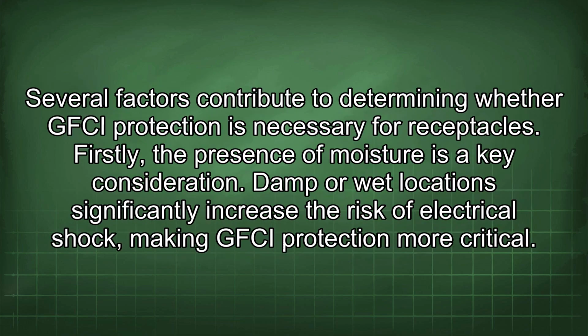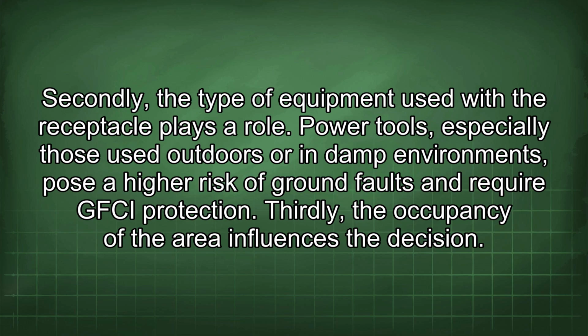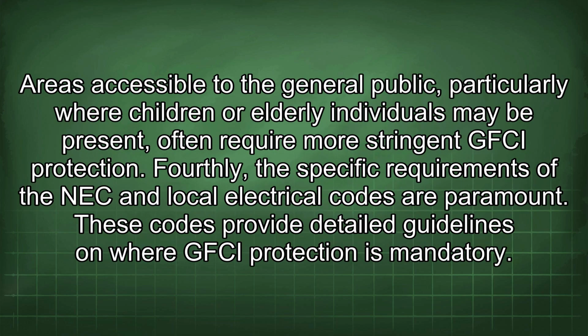Several factors contribute to determining whether GFCI protection is necessary for receptacles. Firstly, the presence of moisture is a key consideration. Damp or wet locations significantly increase the risk of electrical shock, making GFCI protection more critical. Secondly, the type of equipment used with the receptacle plays a role. Power tools, especially those used outdoors or in damp environments, pose a higher risk of ground faults and require GFCI protection. Thirdly, the occupancy of the area influences the decision. Areas accessible to the general public, particularly where children or elderly individuals may be present, often require more stringent GFCI protection. Fourthly, the specific requirements of the NEC and local electrical codes are paramount. These codes provide detailed guidelines on where GFCI protection is mandatory.